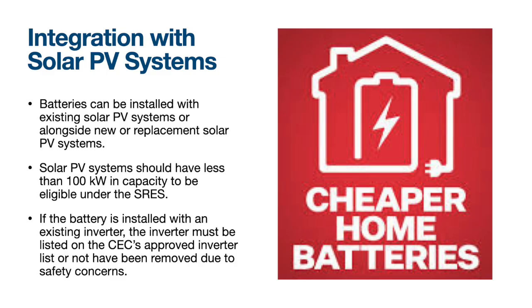They can be installed with existing solar, so it doesn't have to be a new system. You might have solar already on your home and add batteries to it, or you might have no solar at all, but it has to be associated with solar. There's a minimum capacity of 5 kilowatt hours, and as I said, up to 100 kilowatt hours total. If you've really got a big system, the maximum PV size associated is 100 kilowatts, so that's really only commercial customers who'll be up in that range.